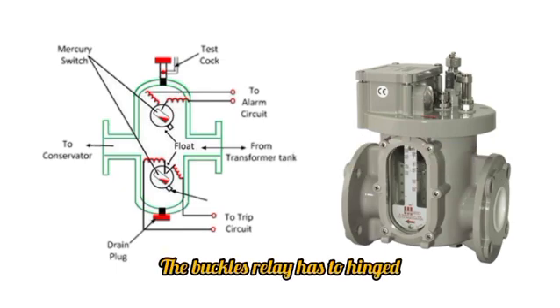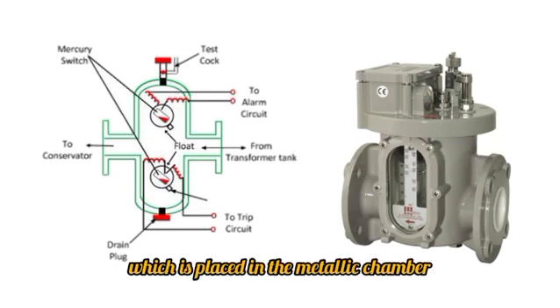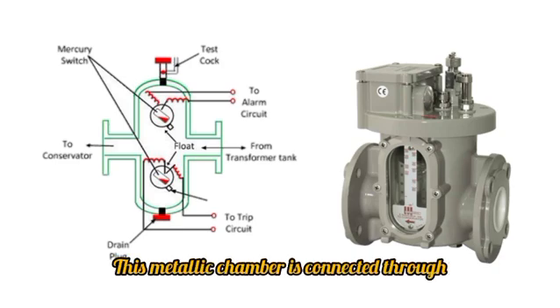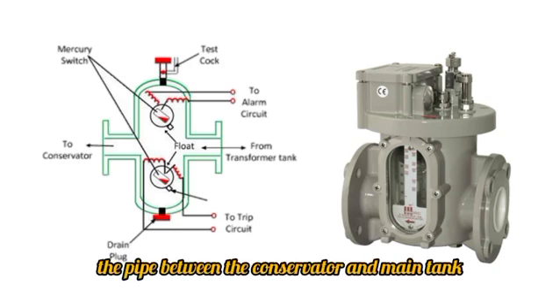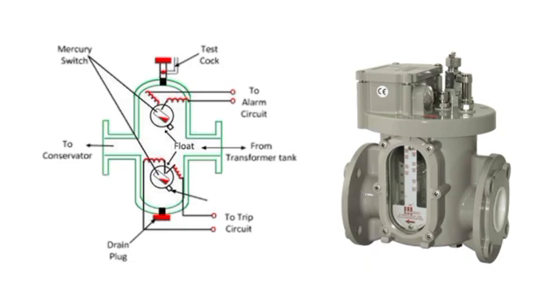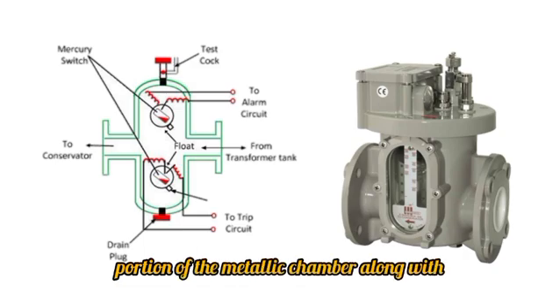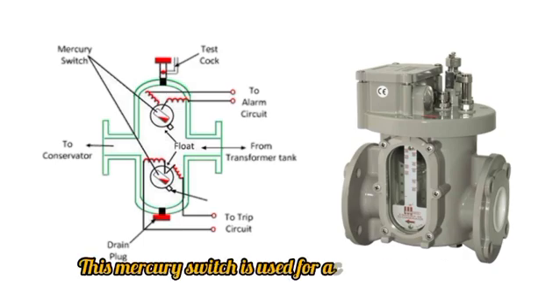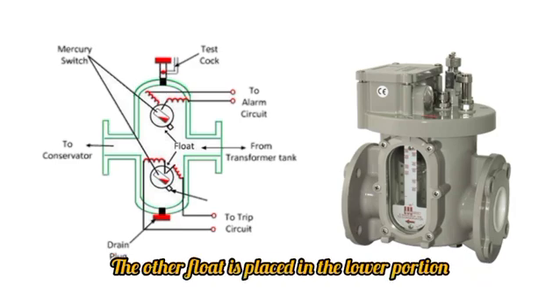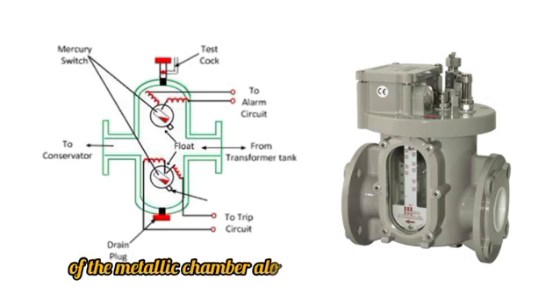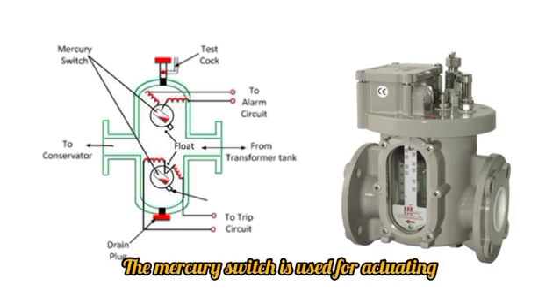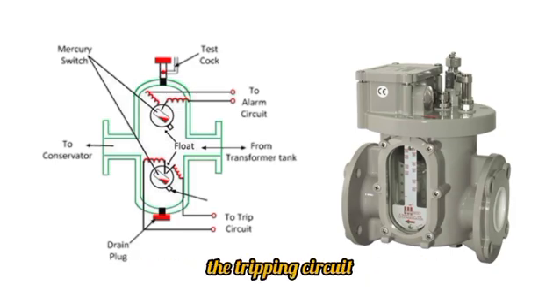Construction of Buchholz relay. The Buchholz relay has two floats, which are placed in a metallic chamber. This metallic chamber is connected through a pipe between the conservator and main tank. One of the floats is placed in the upper portion of the metallic chamber along with a mercury switch. This mercury switch is used for activating the alarm. The other float is placed in the lower portion of the metallic chamber along with a mercury switch. This mercury switch is used for actuating the tripping circuit.